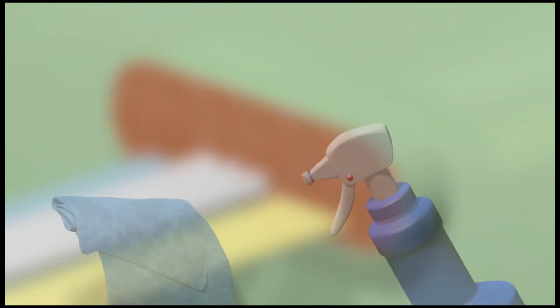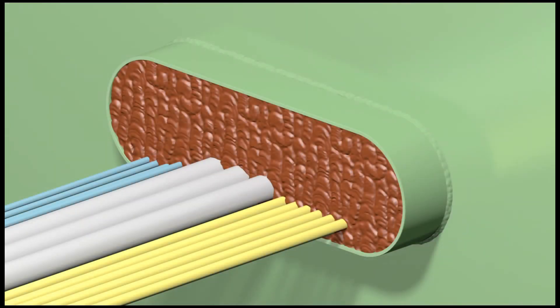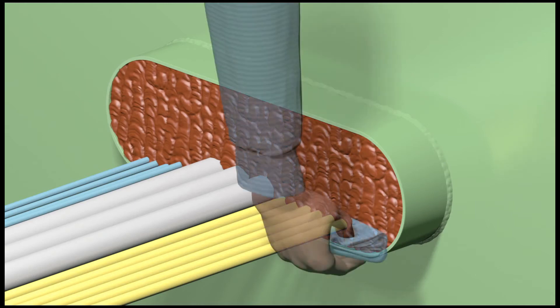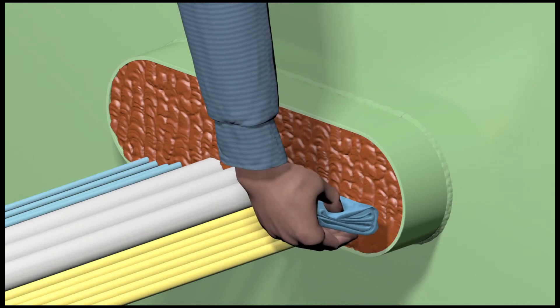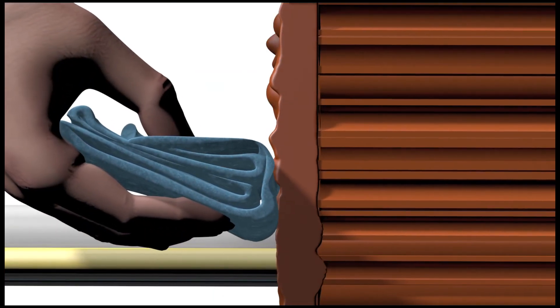To smooth the surface of the Nofirno sealant, a cloth is sprayed with water. This prevents the sealant from sticking to the cloth. Do not use soap water. Soap water will have a negative impact on the adhesive properties of the sealant.